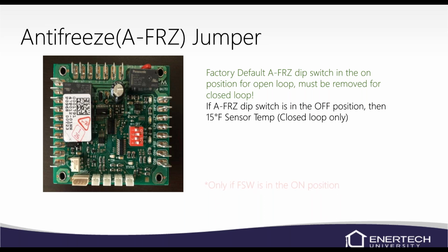So in the on position, that's for an open loop or something with no antifreeze in it. Anytime you're using antifreeze, put it in the off position so it monitors a 15-degree sensor temperature. And again, that's that T4 sensor, the SDT sensor, the source coax temperature sensor.